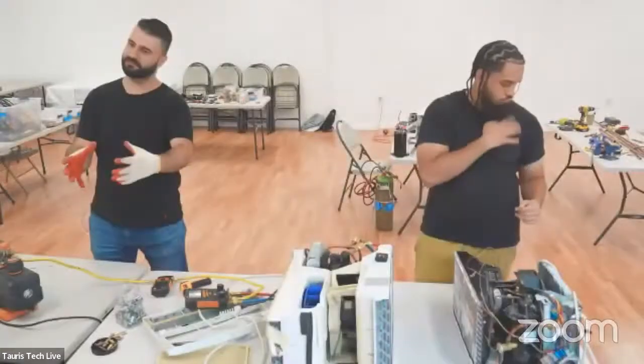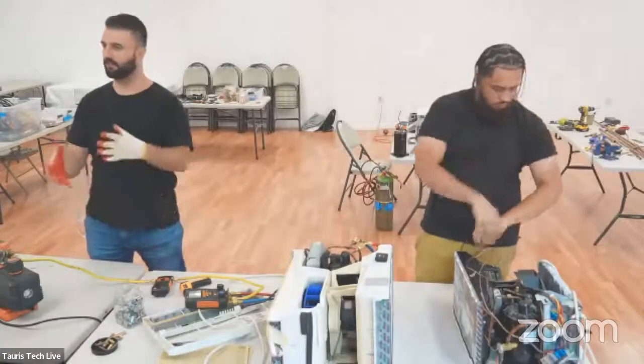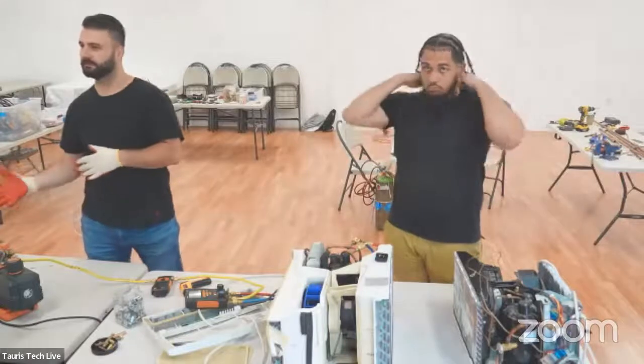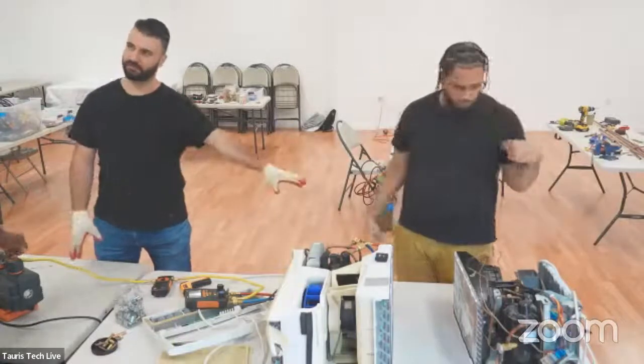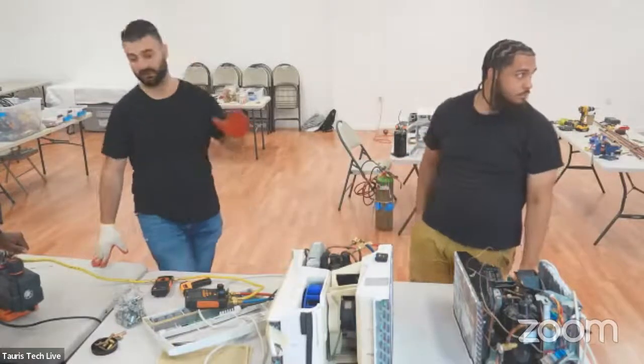That's what it's about. That function was vacuum pump, it was a manual pump. Yeah, and we had a manual purger. So we used to close one valve, then the other valve, wait like 5 minutes, and then purge it to a bottle. So that was the manual purger. When we had a problem, we also used to run the vacuum. Yeah, that's the way it works.